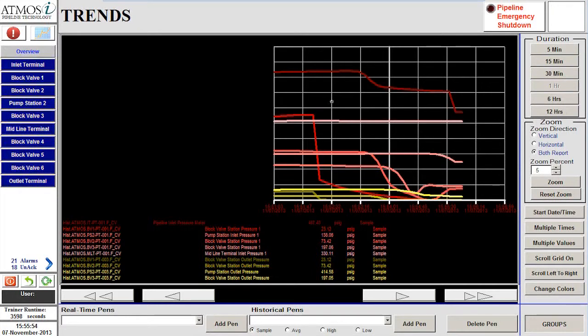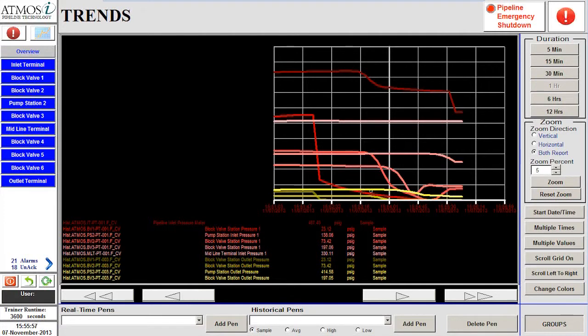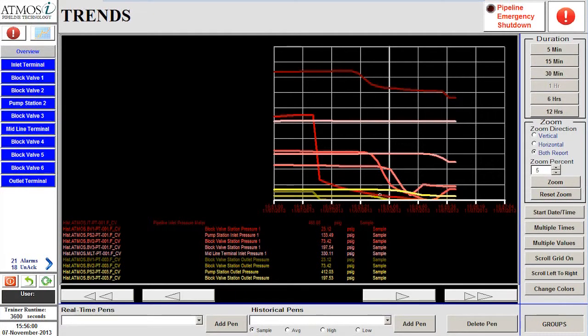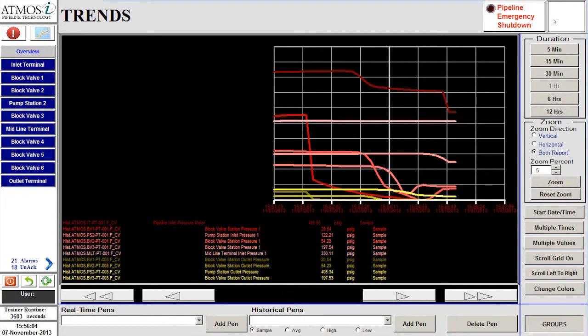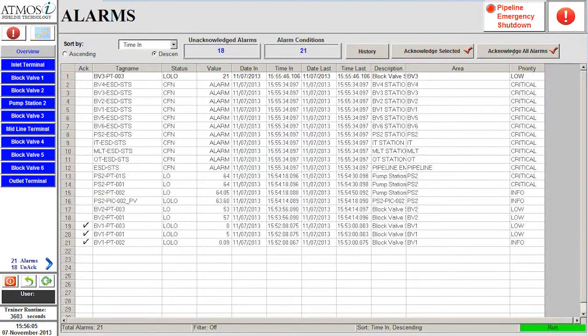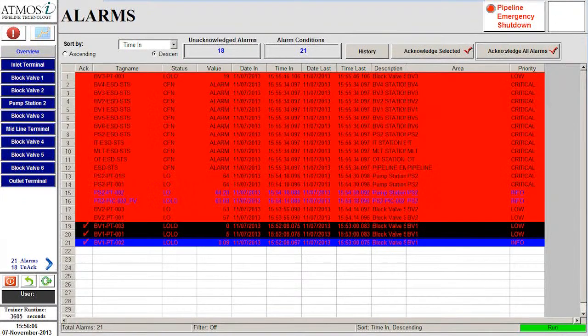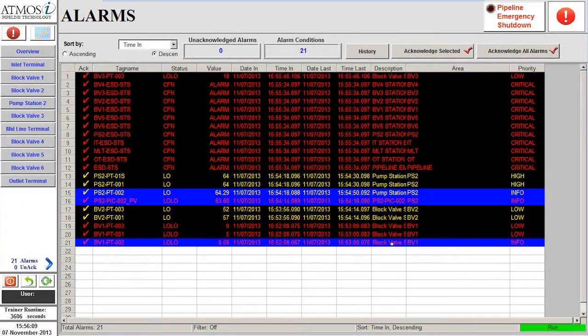At this point, we might want to issue an alert to the appropriate personnel that an event has occurred, which has caused the section pressure to continue to decrease even after the line was isolated. After we have confirmed there is no issue with the other sections and we have determined the section of the event, we can acknowledge the alarms.